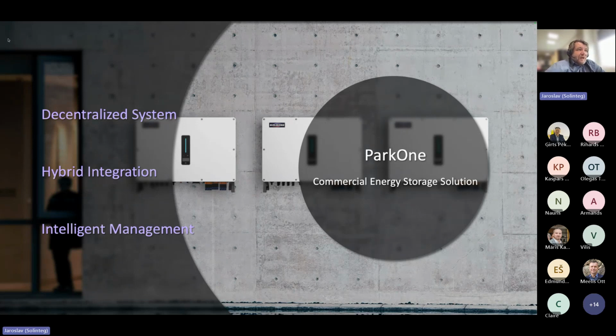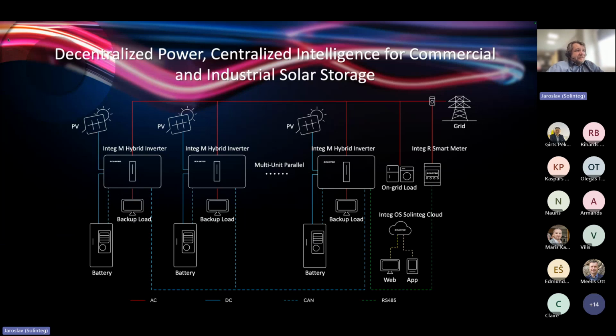We also have a commercial solution, which is the Park One. As you can see, it is a decentralized energy solution. On the inverter side, you can connect up to 10 inverters in parallel. That means a maximum output of 500 kilowatts, and on the battery side, when you are using Solinteg batteries M1, M2, and M3, you can connect about 100 kilowatts to one inverter, so you can make quite a big and powerful storage with just these inverters. The parallel connection of the inverters is very easy. You don't need to buy any special devices. You just connect the master inverter via Modbus to the smart meter and then connect the inverters together over CAN bus. This is very easy and works very well.